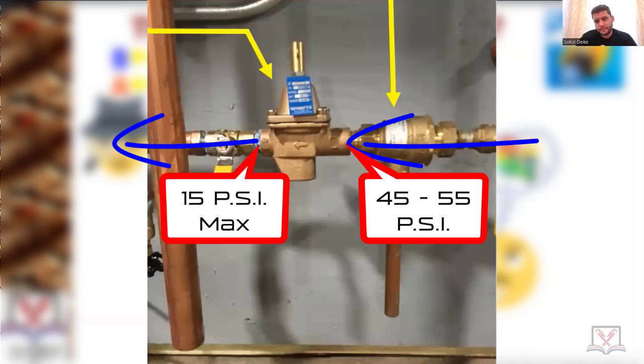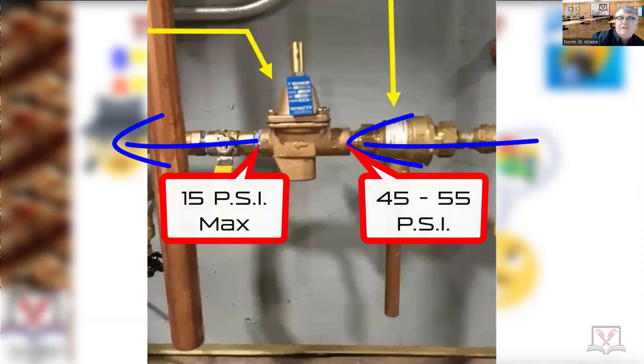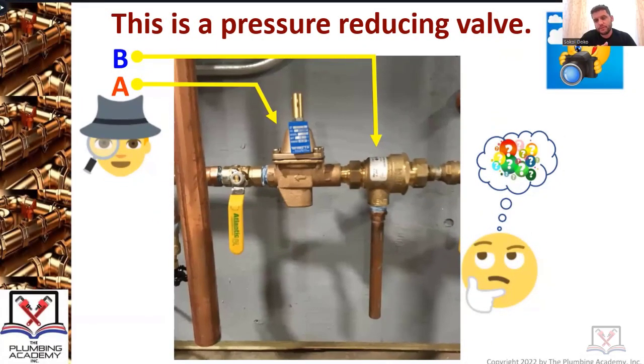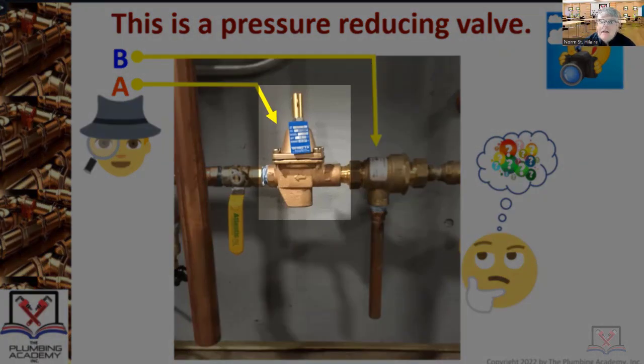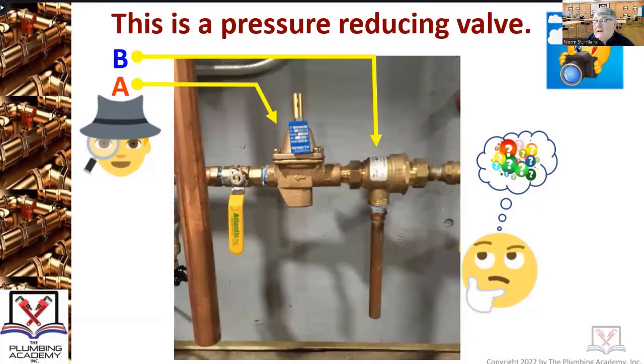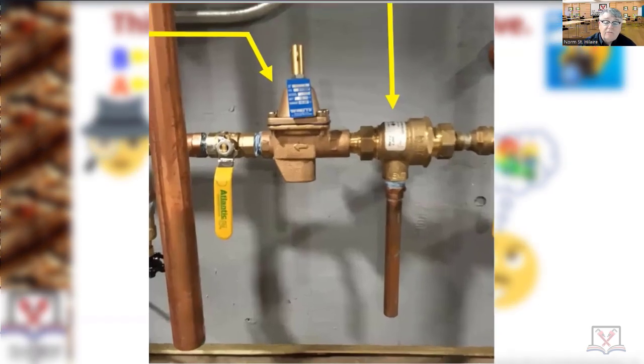15 PSI — very good. So what is it really doing if we're talking about 15 PSI max? If you're going to be a licensed professional and I walk up to you and ask what that device is, you're going to tell me it's a pressure reducing valve — an automatic fill pressure reducing valve. As soon as it feels the pressure go down, it works off a spring and diaphragm. You're using pressure reducing valves when you have over 80 PSI coming into the building; this is a small version to make sure we have 15 PSI and keep water in the boiler.